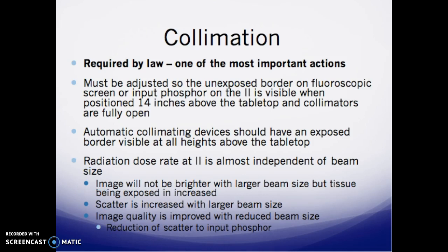Collimation is required by law and is one of the most important actions referenced in the syllabus. It must be adjusted so the unexposed border of a fluoroscopic screen or input phosphor is visible when positioned 14 inches above the tabletop with collimators fully opened. Automatic collimating devices should show an unexposed border visible at all heights above the table. The radiation dose rate at the input phosphor is almost independent of beam size — the image is not brighter with a larger beam, but more tissue is exposed. Image quality is improved by reducing beam size, as scatter to the input phosphor is reduced.